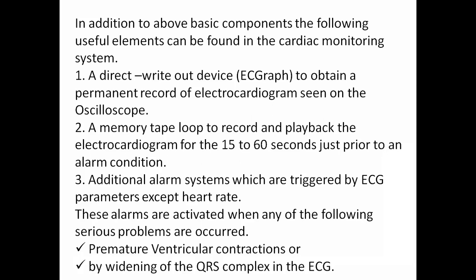a memory tape loop to record and play back the electrocardiogram for 15 to 60 seconds just prior to an alarm condition. Suppose there will also be some memory tapes, and those will record the electrocardiogram, and we can also play back that information when, suppose, something happened in the night.